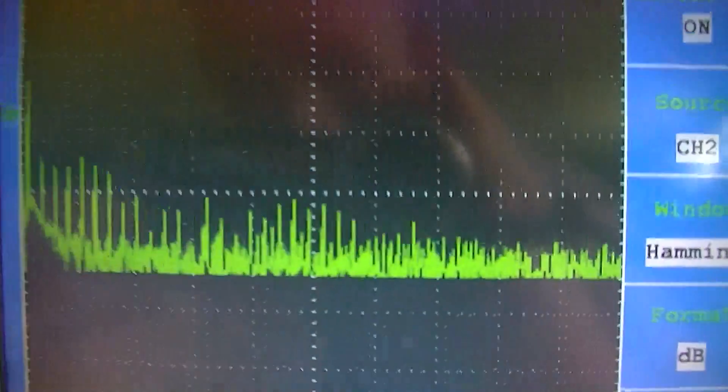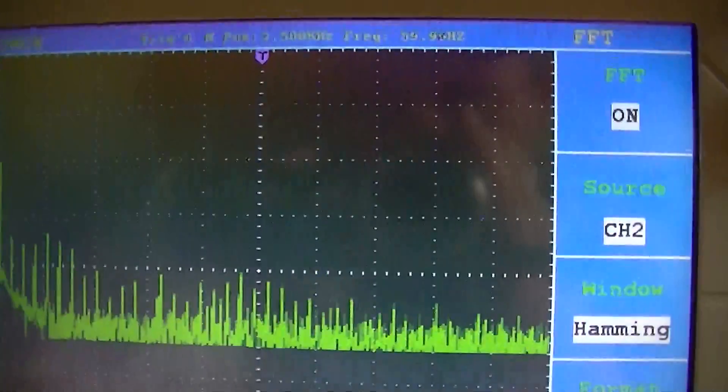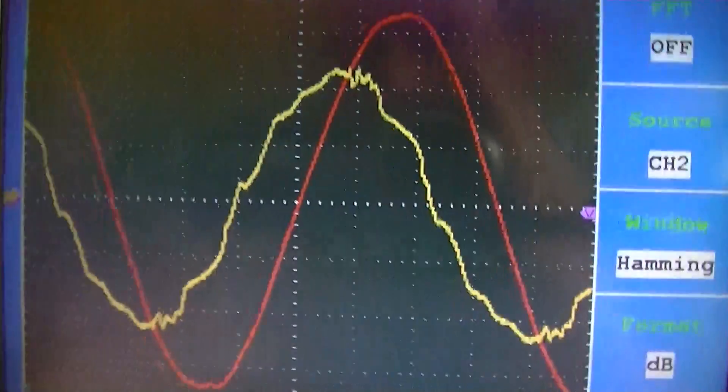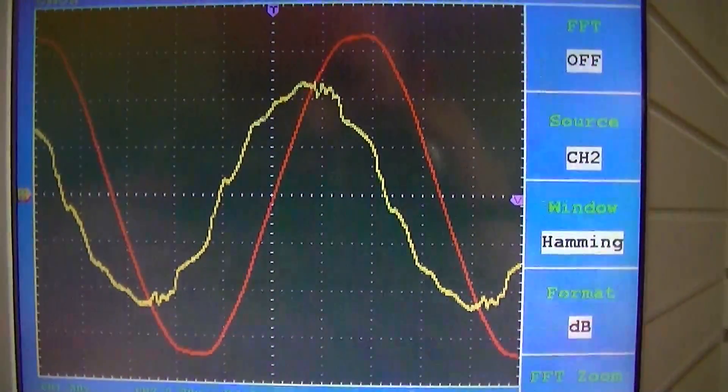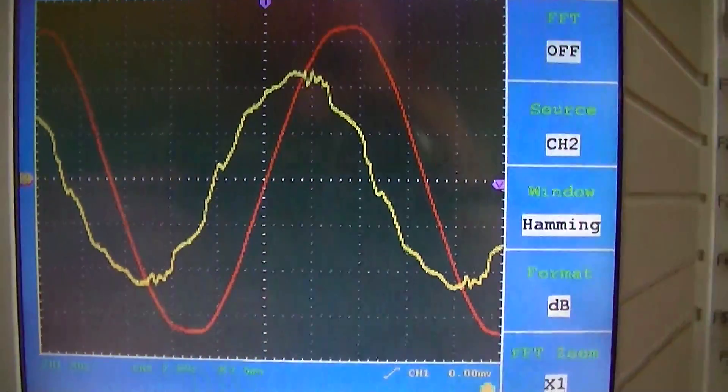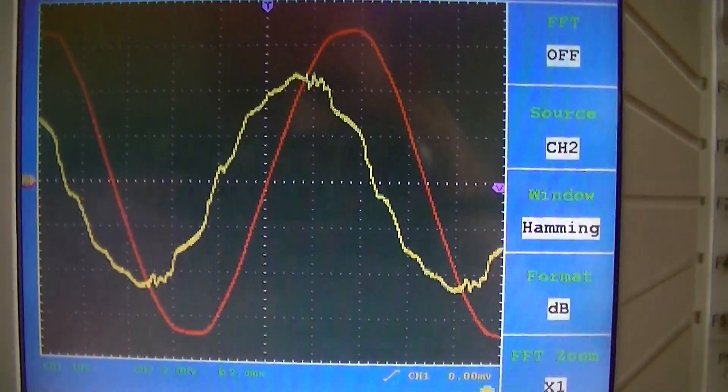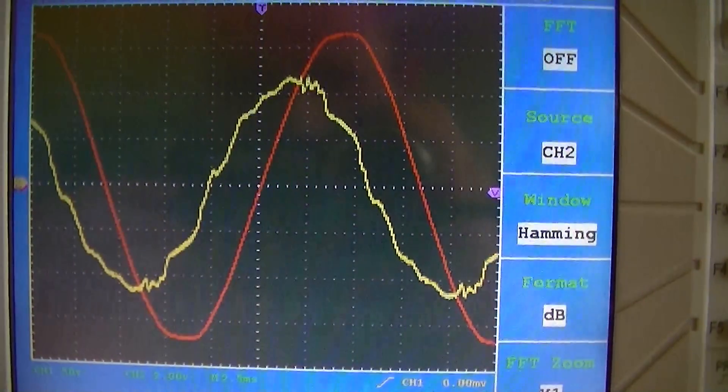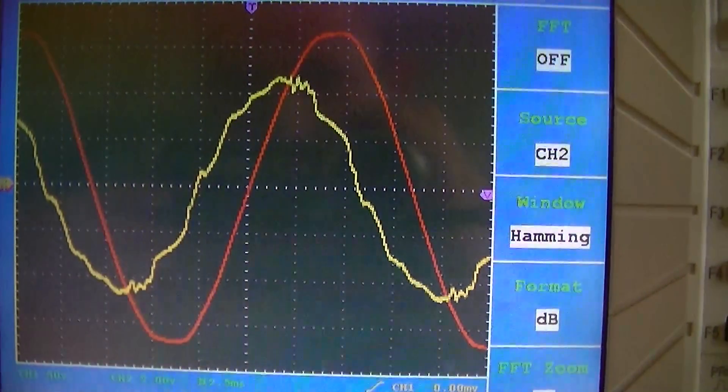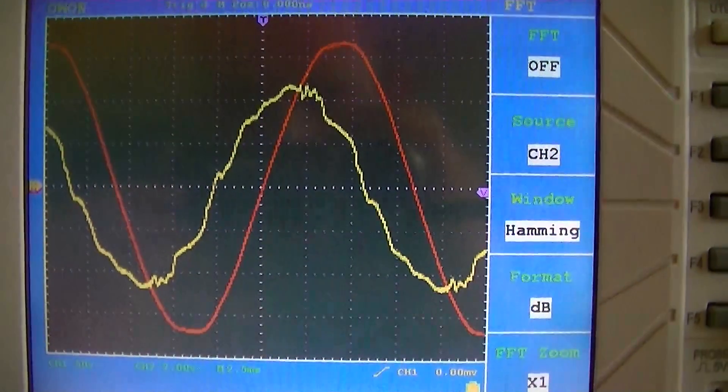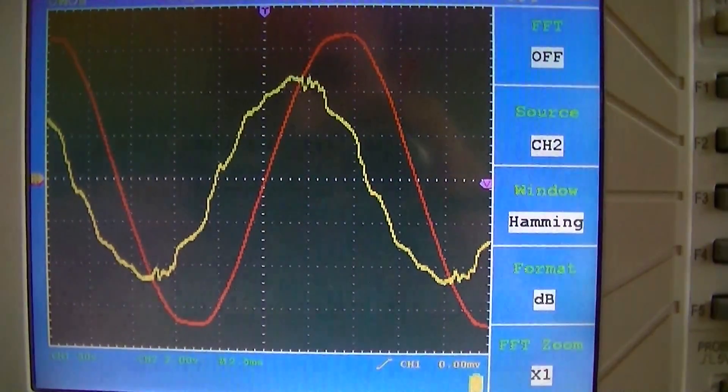You can see we're on 500 Hz per division in the horizontal direction right now. FFT is going off, and that's what our current waveform looks like. We have a very, very different current waveform. That's what I've noticed when you put these capacitors on circuits—you get a very distinctly different current waveform going down that circuit, and it seems to increase the low order harmonics on the system.